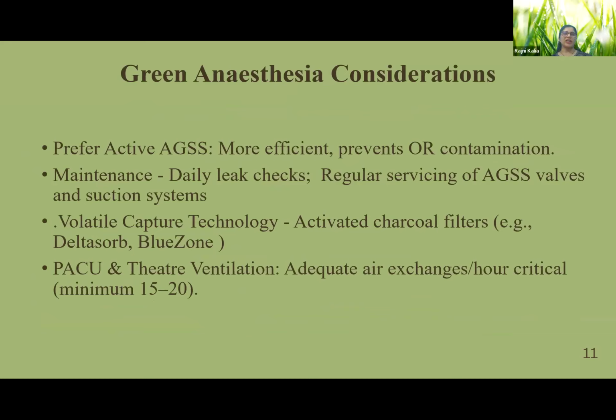Not only is the active anesthesia gas scavenging system important, definitely more important is the maintenance, so that we have to do the daily checkups, regular servicing of the AGSS valves, and the use of activated charcoal filters, and the adequate air exchanges that have to be 15 to 20 per hour.